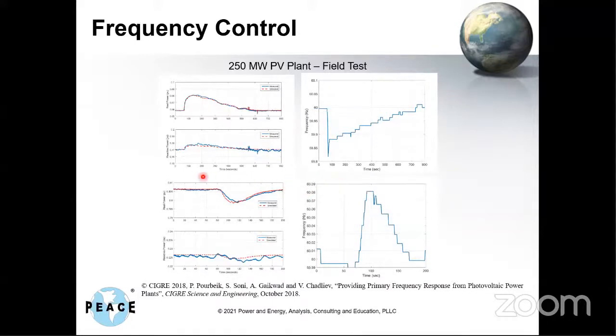Obviously in this case you don't have to have anything in reserve, it could be at the maximum power tracking point, because you're just decreasing megawatts out of the plant. But if you want the ability to respond to an under-frequency event and you don't have any battery energy storage or anything in the plant, then you must always operate suboptimally, keeping some megawatts in reserve. That has economic consequences because you're not generating all the power that's available to you.